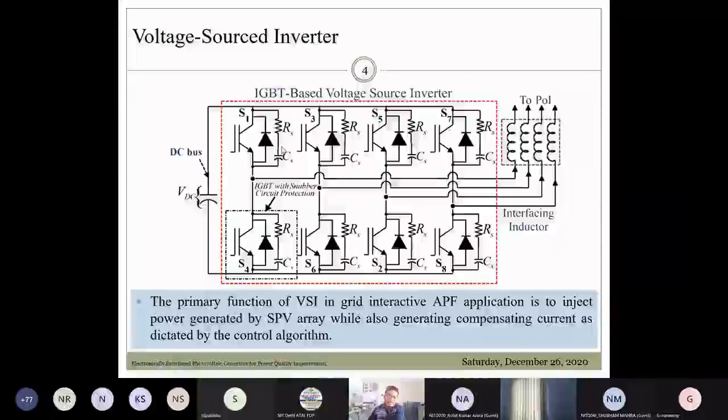In practice, the grid interfaced PV system frequently experiences load perturbation and solar intermittency. As a result, the voltage across the switch may exceed its permissible limit. Therefore, to safeguard the power electronic switch, an RC snubber circuit is used. In this case, when the switch is subjected to a high voltage, dV/dt triggering may occur.